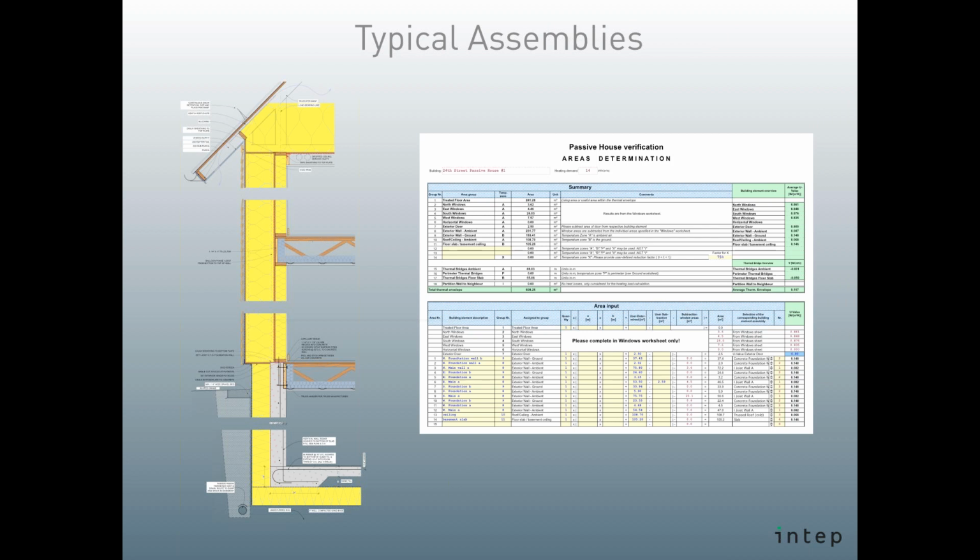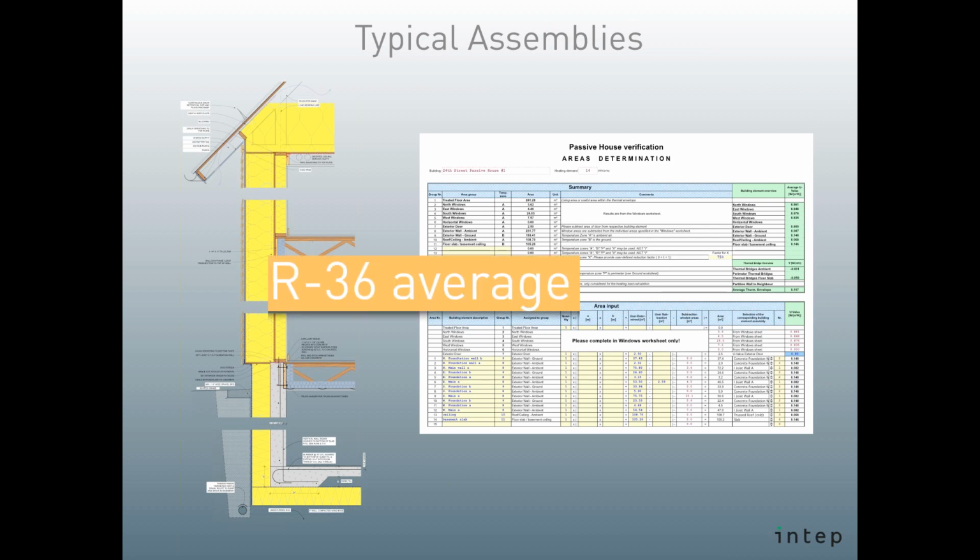I'll tell you a little bit about how this thing will be built then. You can see a section cut through the structure here on the left. And then again, on the right-hand side, a screenshot from the energy model where all these inputs are reflected. The average building envelope, if you take windows and everything that we have here, is insulated to an R36, which is actually not outrageous. If you compare it to the R19 nominal value for maybe the traditional code building, although that doesn't account for thermal bridges, and this does.